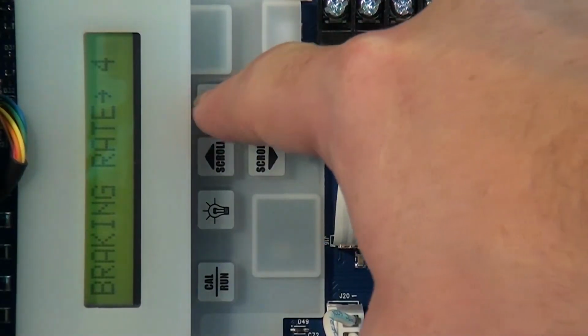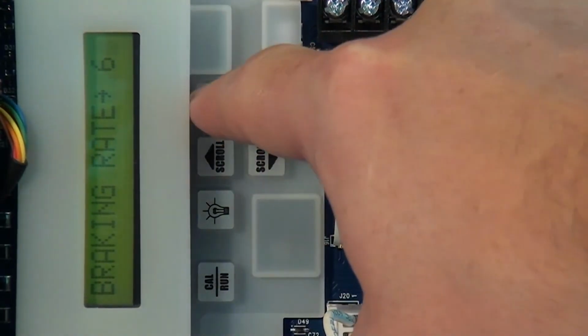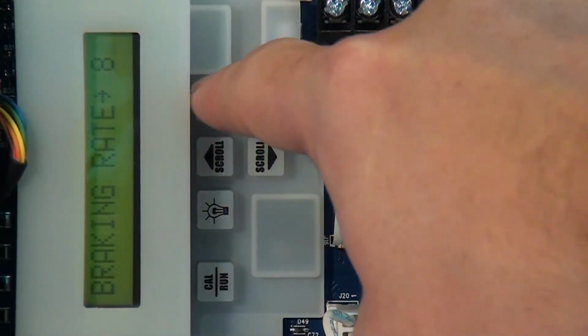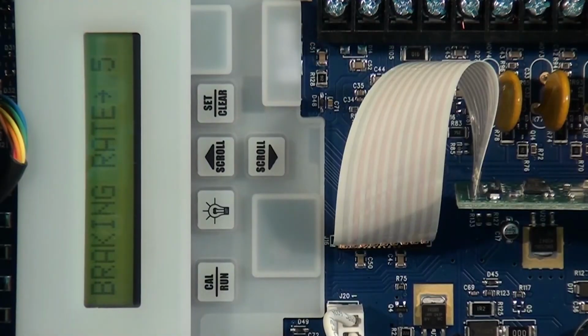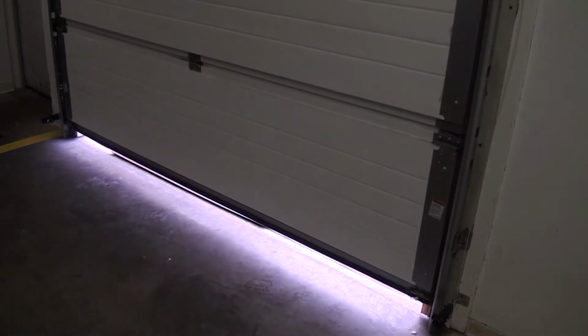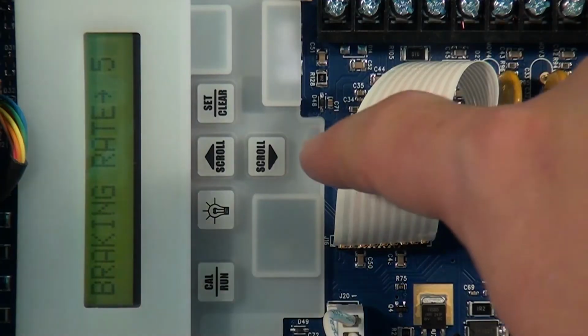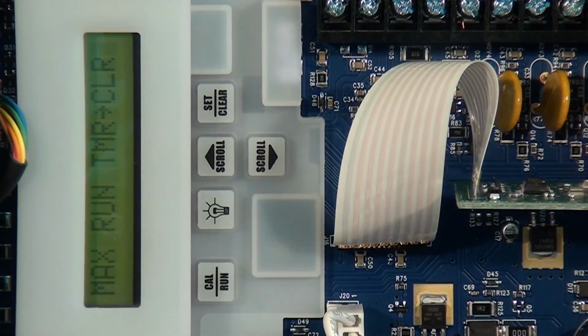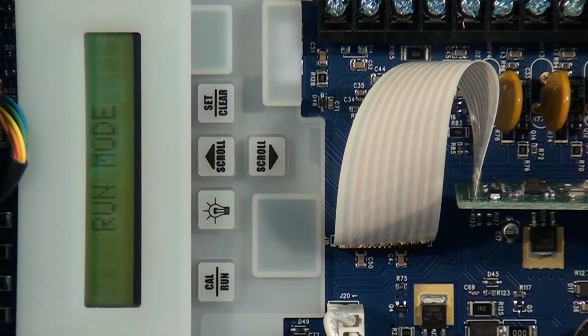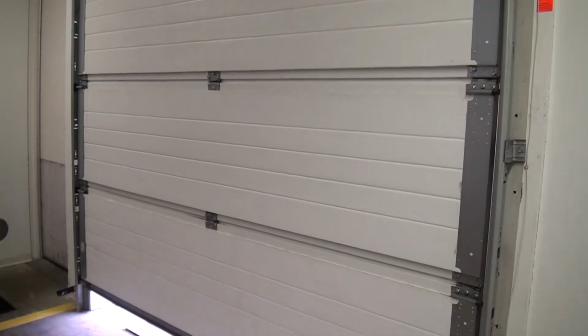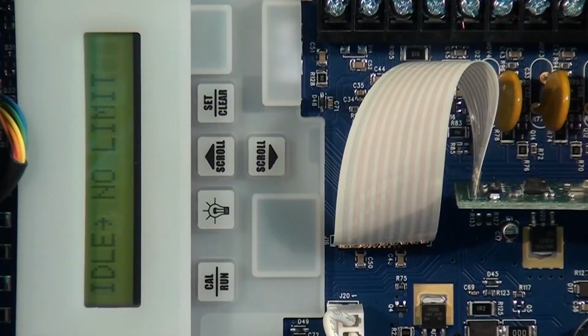This is a trial and error adjustment depending on the application. 0 is the maximum braking rate and 9 is the minimum. Pick a value and operate the door. Adjust as necessary. Press either scroll key to lock in the selected braking rate. Press the calibration run key to return to run mode. Now let's program the open-close limits. If the operator is in run mode, press the calibration run key to enter the calibration mode. Otherwise, skip to the next step.